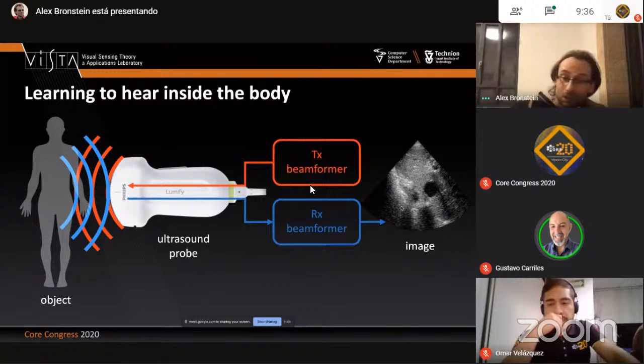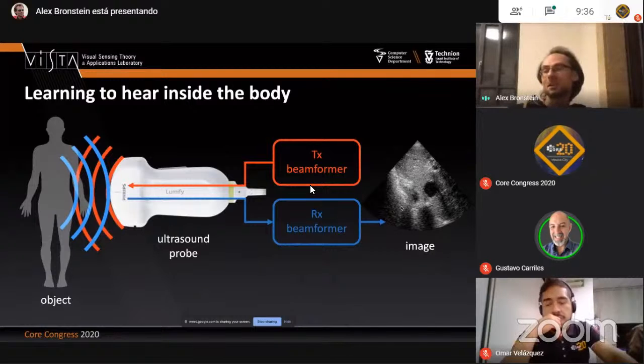The way it works, you typically send RF signals in the range of several megahertz to an array of crystals that oscillate and create an ultrasonic wave. That wave is focused inside the body. It reflects from the transitions in the acoustic impedance in the body, like different tissues, bones, and so on. And then we capture the reflected wave, and we transform it into the image. So the creation of this pulse, essentially we need to create amplitudes and phase delays to focus the beam with that phased array of crystals. This is called transmit beamforming. And on the way back, we also need to do receive beamforming in order to create an image. This is how ultrasound works.